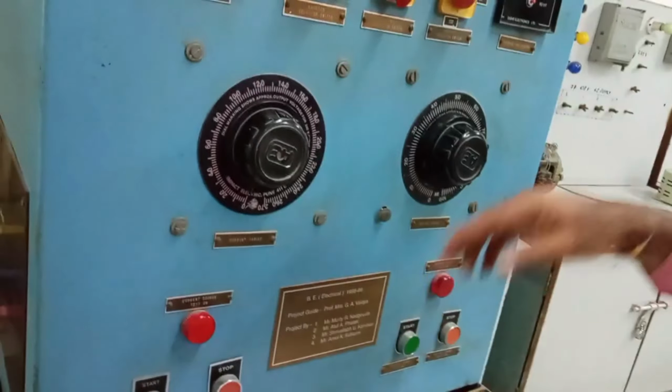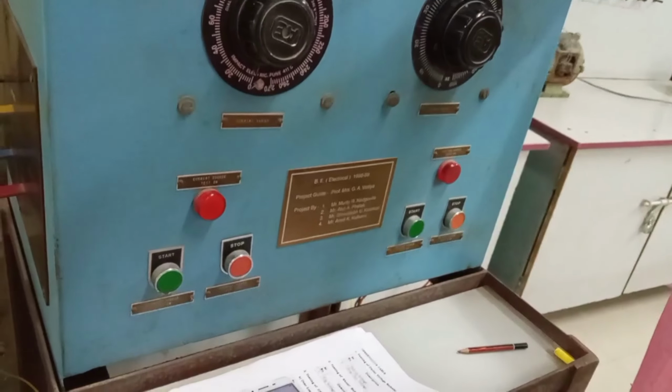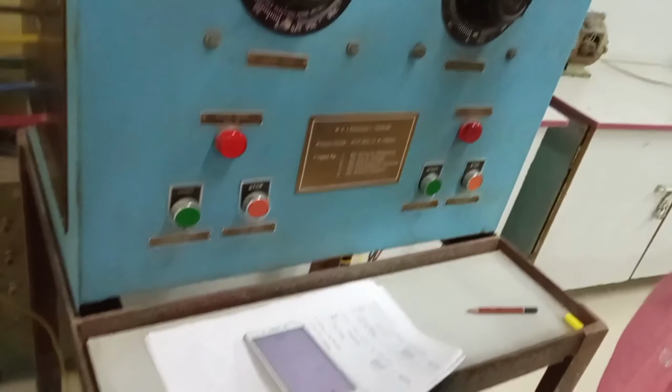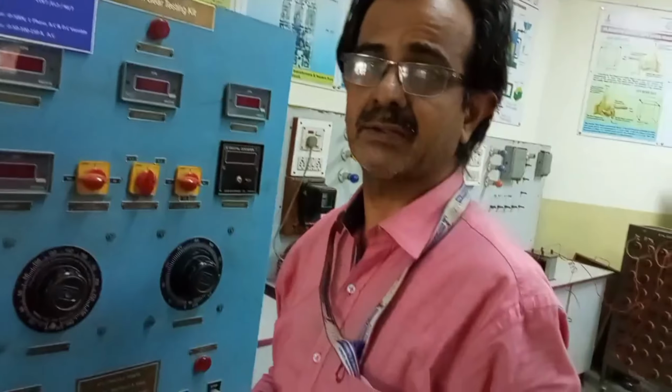See, the breaker tripped instantly, you might have heard that. See, the breaker is in an open position now. As soon as I started injecting the current, at the same time I got the tripping of the breaker. So in this way we can say that the breaker trips instantly within a fraction of a second. Okay.